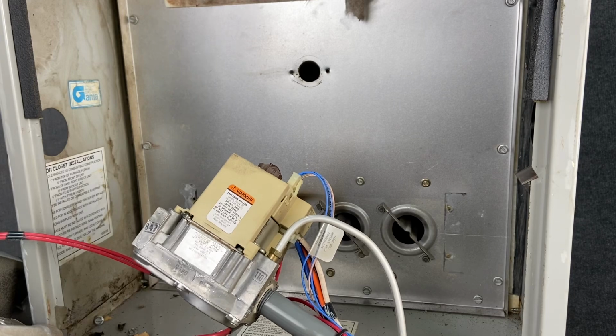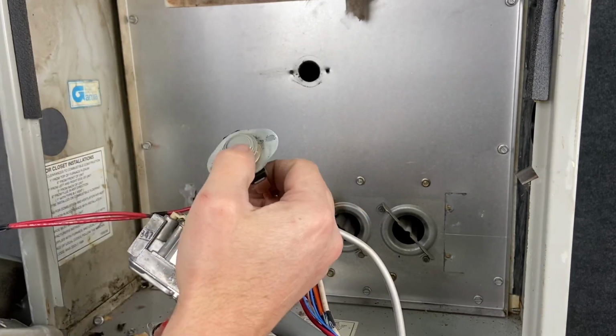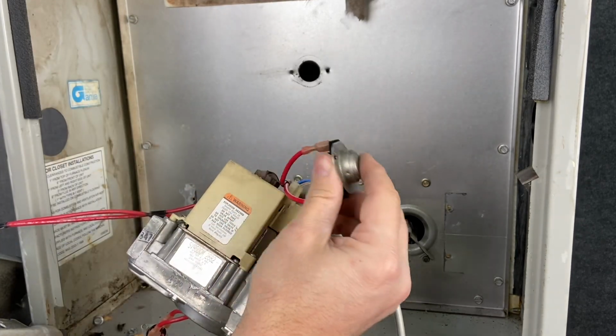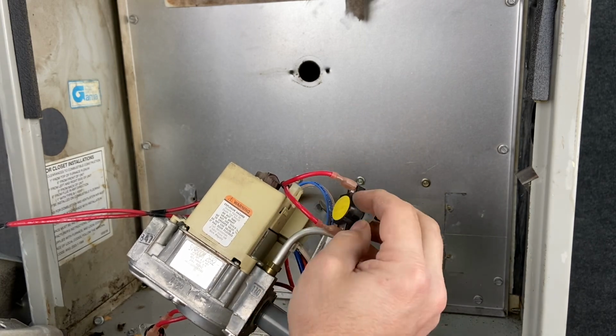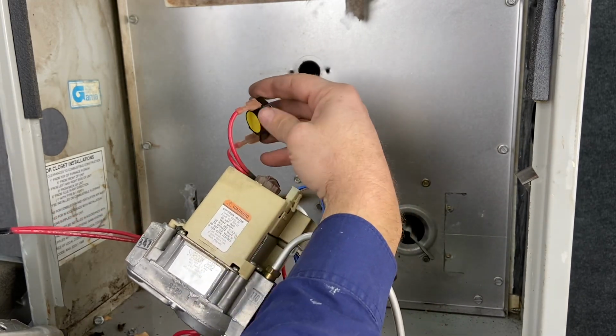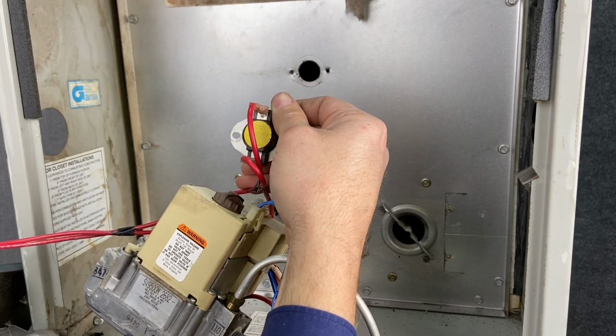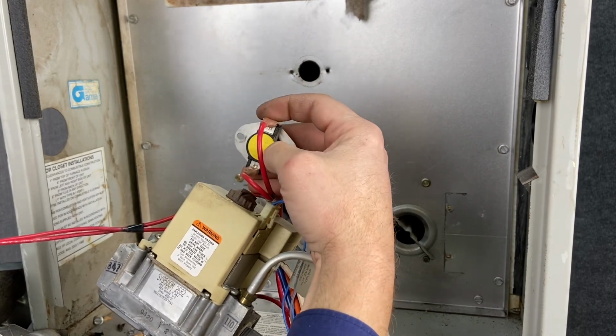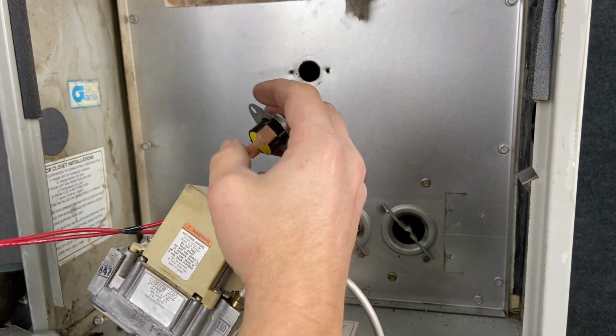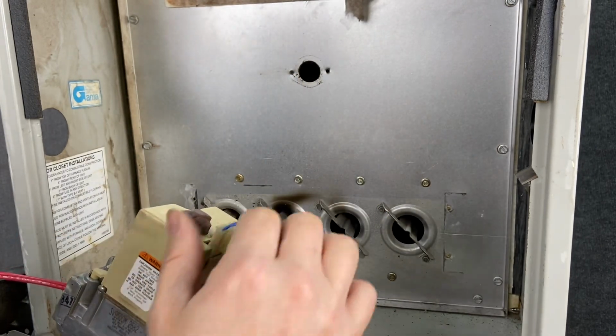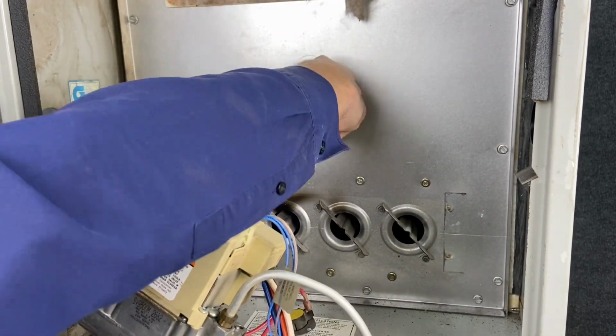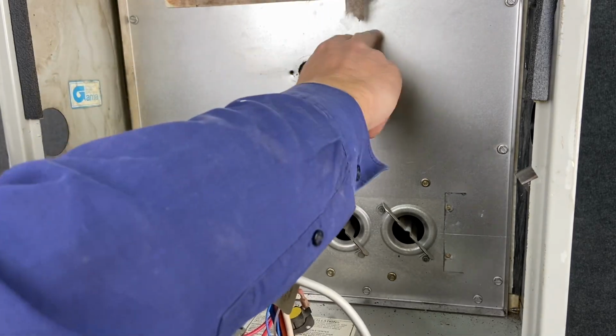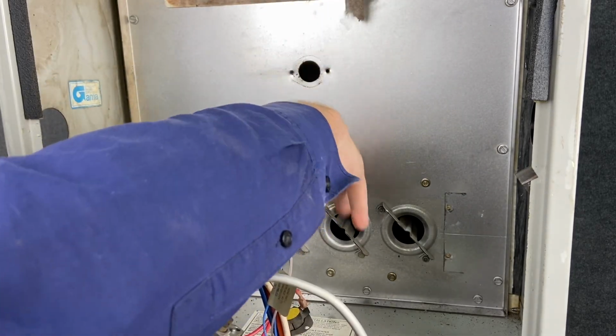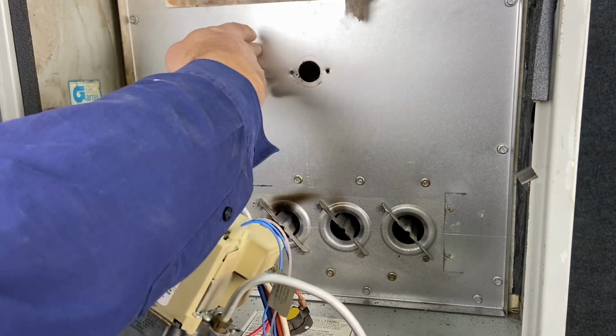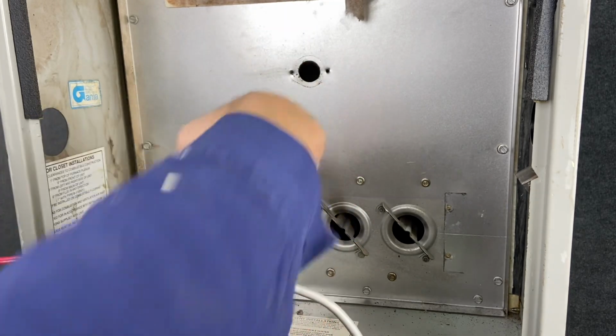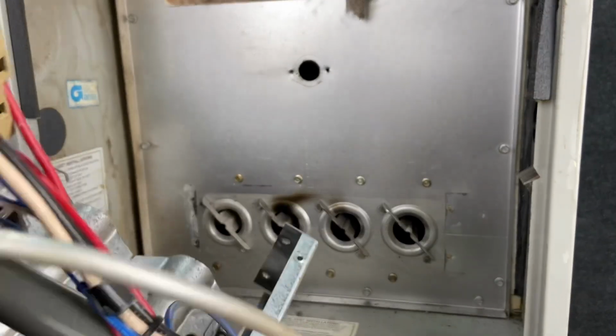Now these are automatic resets, and on this one I can't manually press it in, but when this gets too hot, it opens the limit. And this one may or may not say the reading on it. It's hard to see it on here, but it should say the limit that it closes and how many degrees before it opens back again, or vice versa. If you look through this hole here, it's right between the heat exchangers. It's not on the metal itself, it's right between it. So if the airflow stops going, this is going to radiate heat out of both sides to the limit, and then this limit opens. So what we have is this whole assembly out.